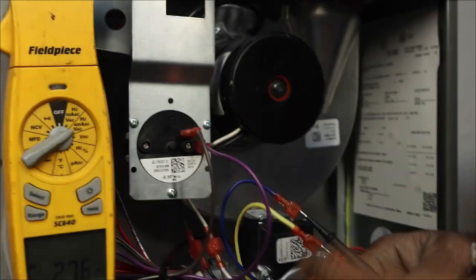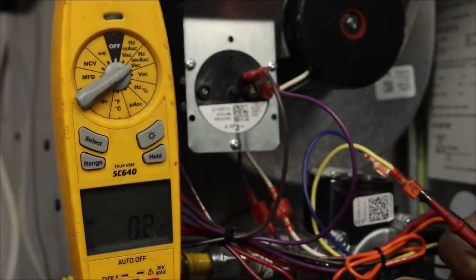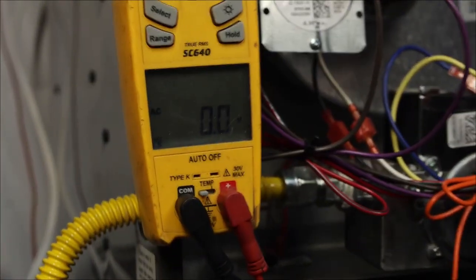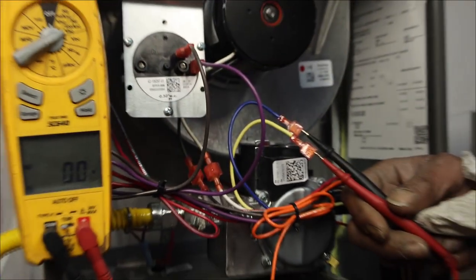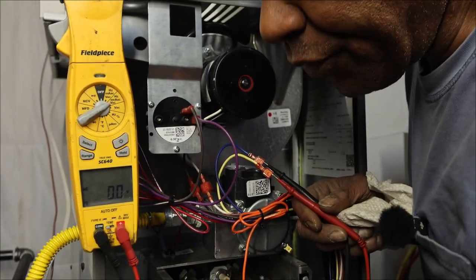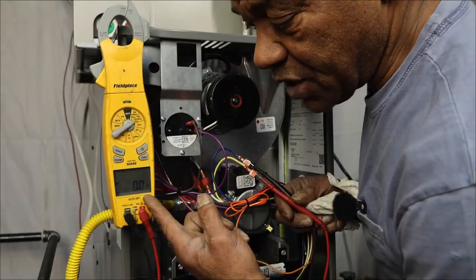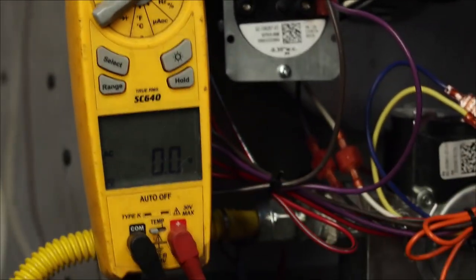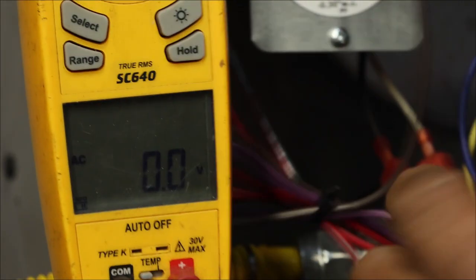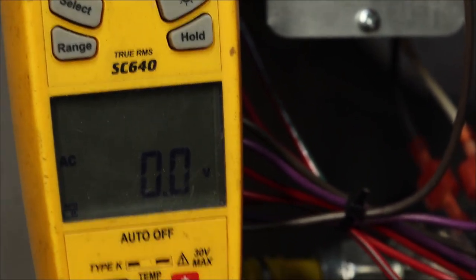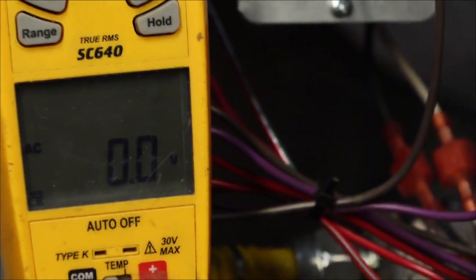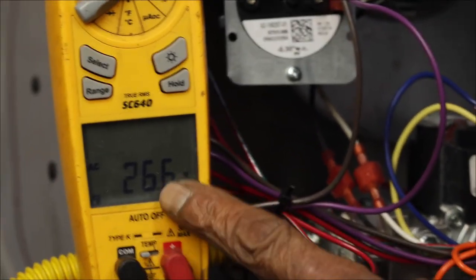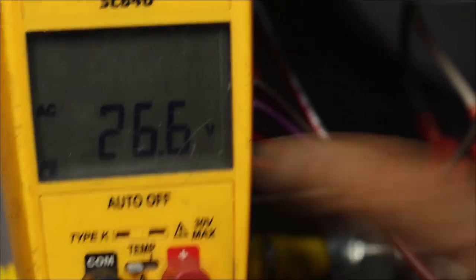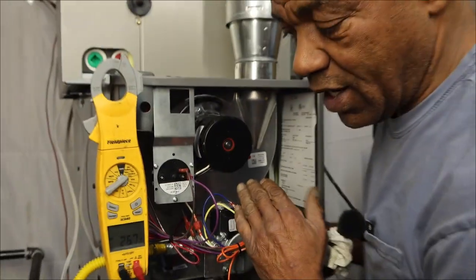Now my unit, it went through the cycle once. It just went through the cycle again. Spark igniter, it's going through the cycle a third time. The spark igniter will energize. You'll hear it clicking, and then you'll see it sends 24 volts to the circuit board. To the gas valve. When you hear the click, that simulates the circuit board sending power to the spark igniter, and then send power to the gas valve so the gas valve can energize and light.